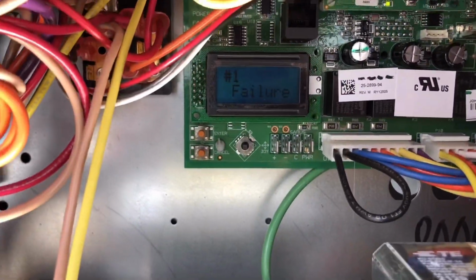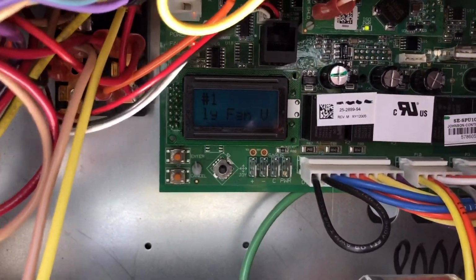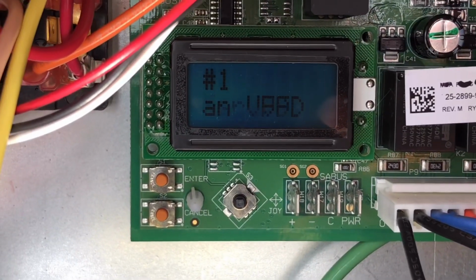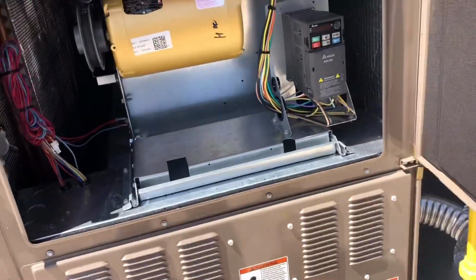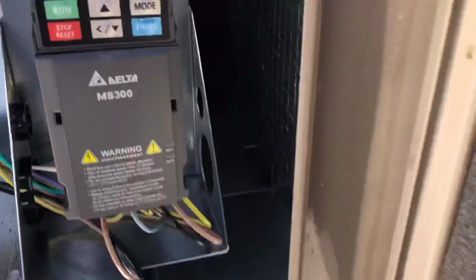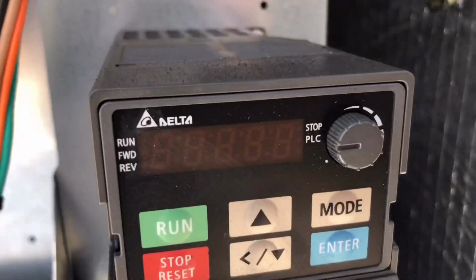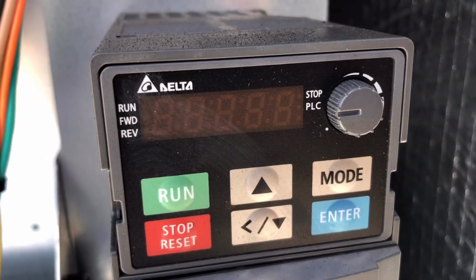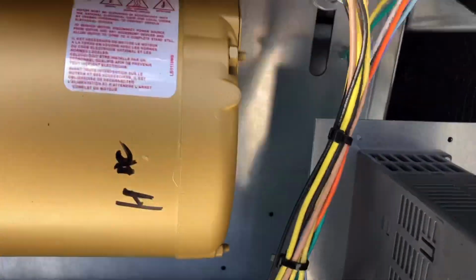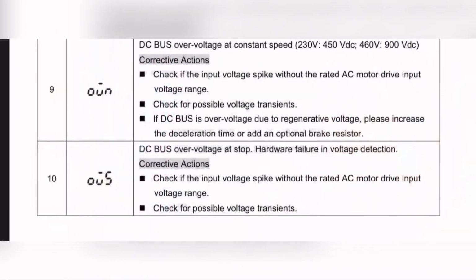Right there, VFD failure, supply fan. Looks like we're gonna have it, number 1, supply fan VFD failure. Let's go ahead and check it out real quick. Fan, my VFD, it's got an alarm OU5. I'm not sure what that means.